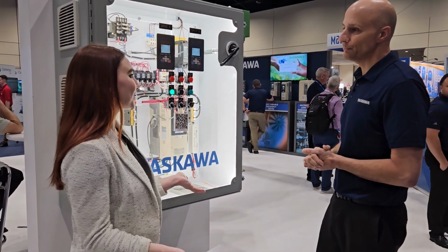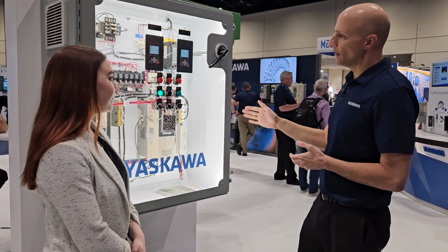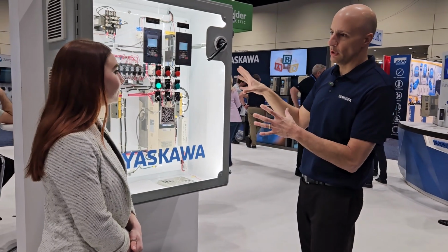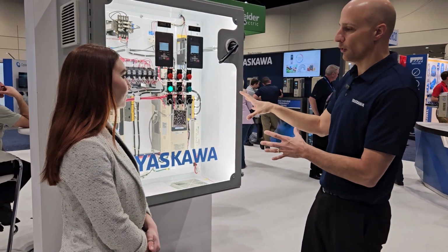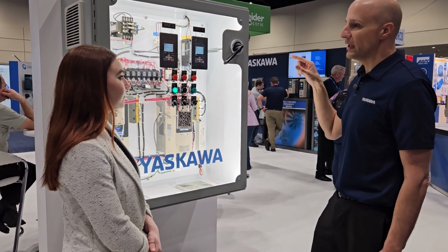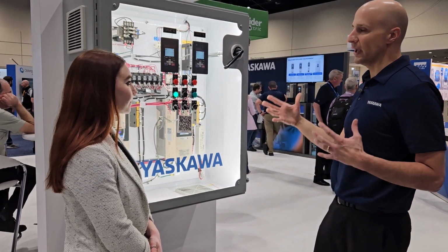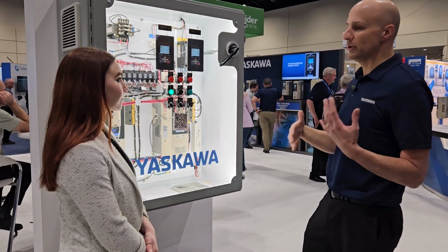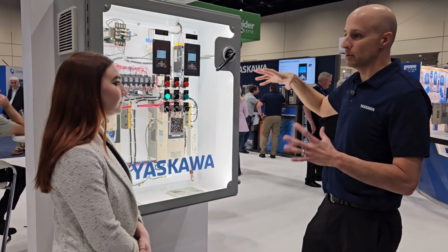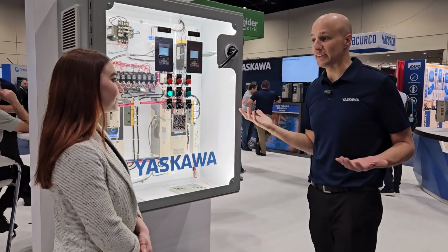Very nice, very nice. Is there anything else that you wanted to tell me about variable drives or about what you're showing today? Well, this is probably a type 1. This is a custom panel for the show here. We don't build these in a 200 volt class, but in the 460 volt class, we have type 1, and new for HV600 is the type 12 enclosure. We didn't offer that before, so that's a nice feature. And type 12 would be for maybe a dusty, dirty environment. Maybe you have some condensating pipes with water dripping that's going to be more tolerant to that kind of environment. So that's kind of a nice thing that we offer as a standard product now.